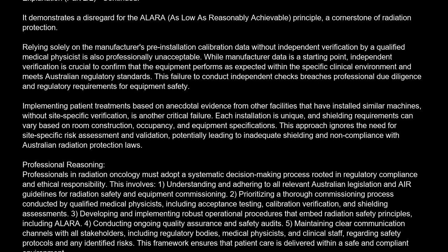Professionals in radiation oncology must adopt a systematic decision-making process rooted in regulatory compliance and ethical responsibility. This involves: 1. Understanding and adhering to all relevant Australian legislation and AIR guidelines for radiation safety and equipment commissioning. 2. Prioritizing a thorough commissioning process conducted by qualified medical physicists, including acceptance testing, calibration verification, and shielding assessments. 3. Developing and implementing robust operational procedures that embed radiation safety principles, including ALARA. 4. Conducting ongoing quality assurance and safety audits. 5. Maintaining clear communication channels with all stakeholders, including regulatory bodies, medical physicists, and clinical staff, regarding safety protocols and any identified risks. This framework ensures that patient care is delivered within a safe and compliant environment.